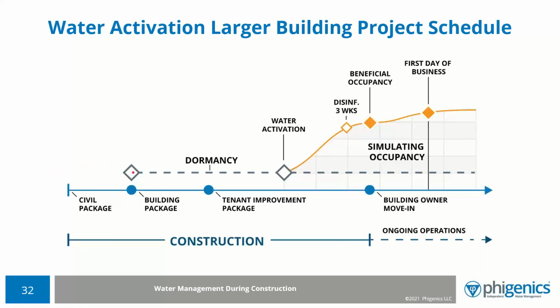At some point that civil package is complete, it gets flushed and tested for coliforms and E. coli, then it's parked and sits, not reactivated until later when the tenant improvement package is complete. We often find this system just sits dormant, and someone activates it and brings all that dormant water that's been sitting for months or a year into their building water system. Terrible idea. You want to flush that first, get rid of the dormancy, get active water at the point of entry, then make the connection.